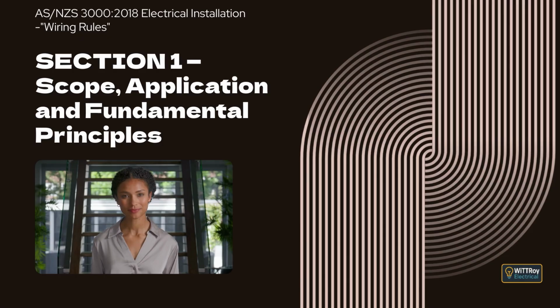Clause 1.6.5 Circuit arrangement. Circuits must be arranged to reduce danger and reduce inconvenience when a fault occurs. They must also allow safe operation, inspection, testing, and maintenance. Clause 1.7.1 General. Electrical equipment must be selected and installed so that it operates safely and reliably under normal conditions. It must not create danger from shock, fire, overheating, or other reasonably expected conditions such as overload or external influences. And the equipment must be installed according to both the requirements of this standard and the manufacturer's instructions.